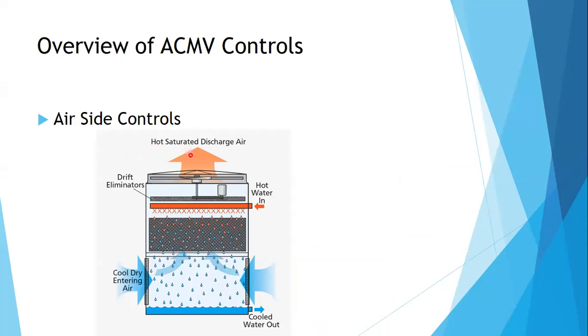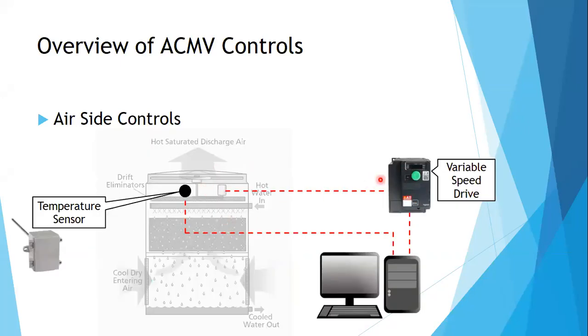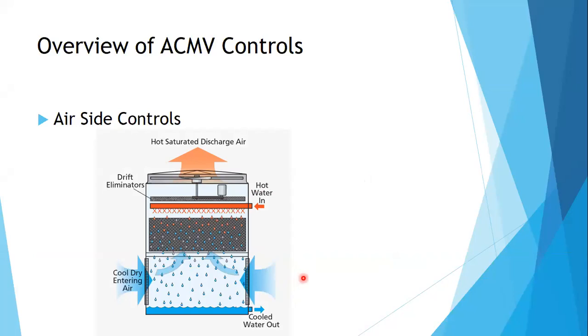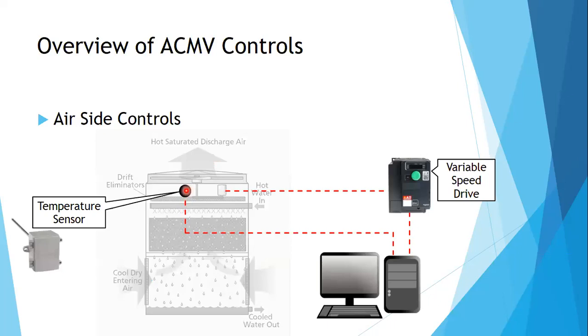Another one of your airside controls is your cooling tower. So how do you control your cooling tower? Your cooling tower also has a variable speed drive. You put your temperature sensor here. Again, where is this one? This is where the cold air goes up, has contact or heat exchange with the water vapors or water droplets, and after that the hot air goes out. So you want to measure this hot air temperature. Based on the hot air temperature, you put your temperature sensor here, you'll be able to send a signal to your BMS, and your variable speed drive will increase or decrease the frequency of your fan motor.